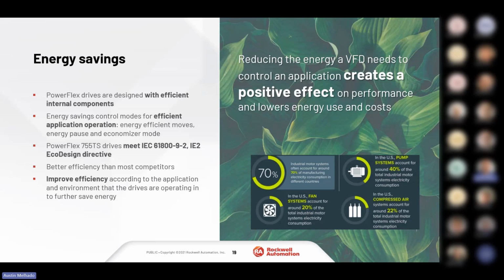So economizer mode consists of the sensorless vector control with additional energy saving functions. When the steady state speed is achieved, the economizer becomes active and automatically adjusts the drive output voltage based on the applied load. By matching the output voltage to the applied load, the motor efficiency is optimized, reducing the command for the motor flux current.